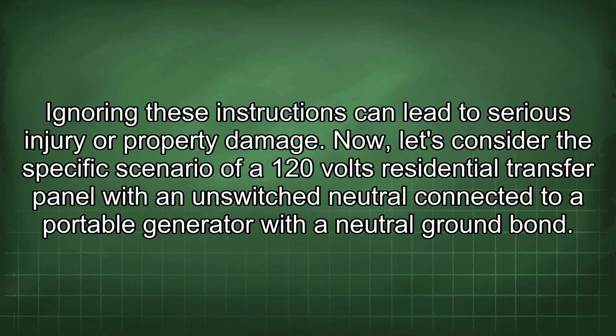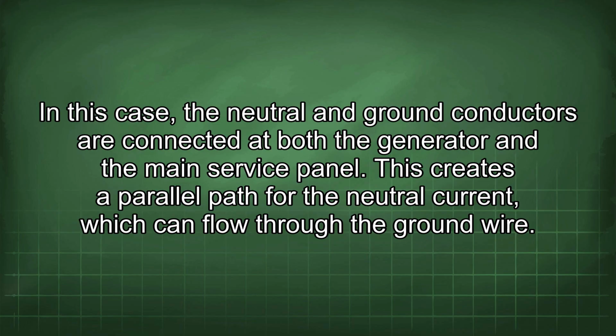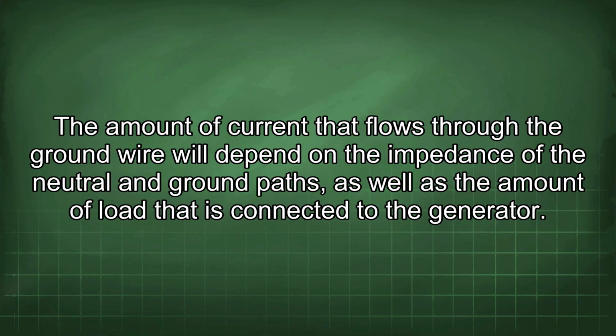Now, let's consider the specific scenario of a 120 volts residential transfer panel with an unswitched neutral connected to a portable generator with a neutral ground bond. In this case, the neutral and ground conductors are connected at both the generator and the main service panel. This creates a parallel path for the neutral current, which can flow through the ground wire. The amount of current that flows through the ground wire will depend on the impedance of the neutral and ground paths, as well as the amount of load that is connected to the generator.